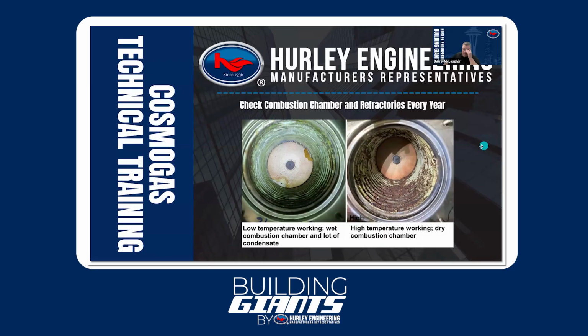On the fire side, this is more typical, like I said, for condensing applications. But if you happen to be running hot all the time, this is what you'll see. Most of it's still shiny. This is just stuff that has dropped out that needs to be cleaned. So as long as you can get this cleaned out, and again, we have the fireside cleaning tools to do that, you'll be fine.